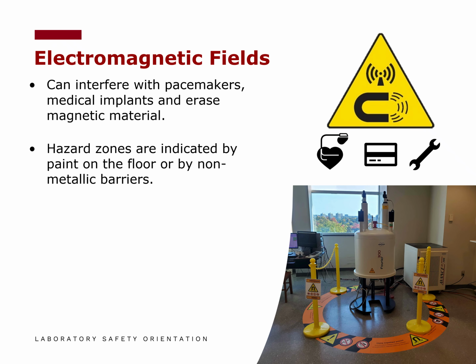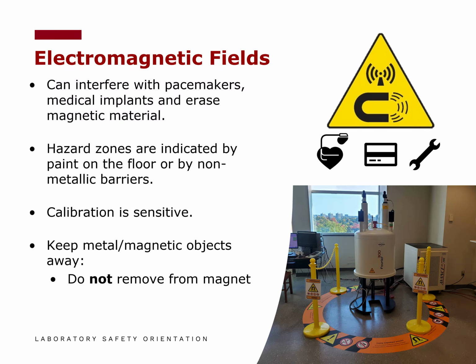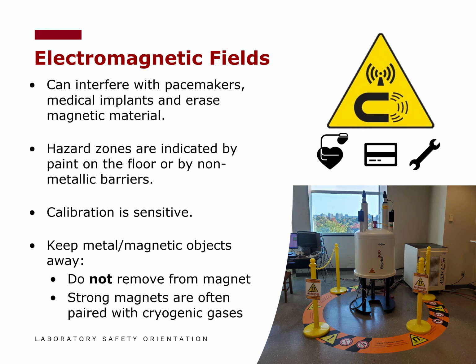NMR and other magnetic systems are extremely sensitive and must not be touched. Calibration can be affected by vibration, interference, or unauthorized contact. One of the most important precautions is to keep all metal and magnetic objects away from the magnet. These items can be rapidly pulled into the magnet with dangerous force. Never attempt to retrieve an object yourself, as you can easily crush and injure fingers or limbs in the process. Instead, immediately contact the NMR facility manager.